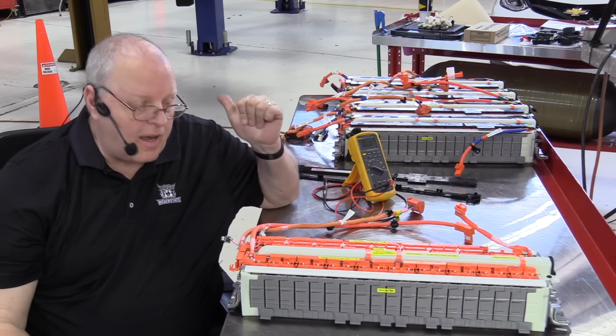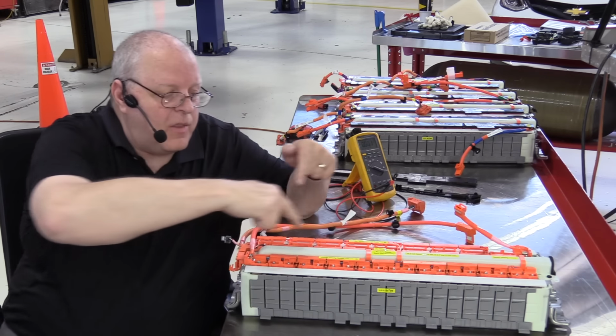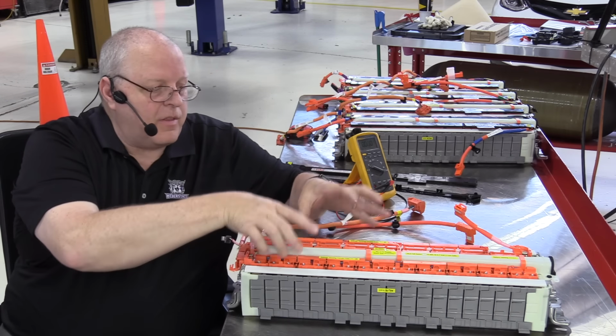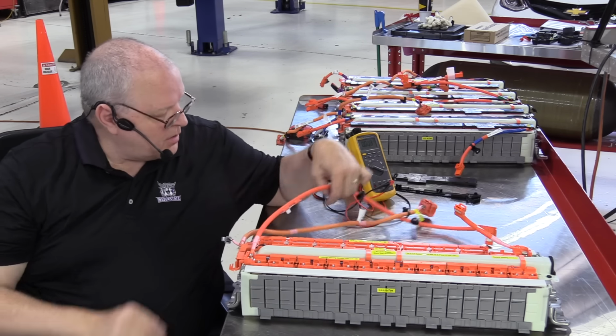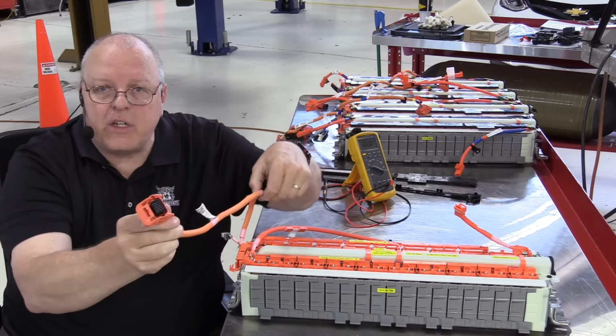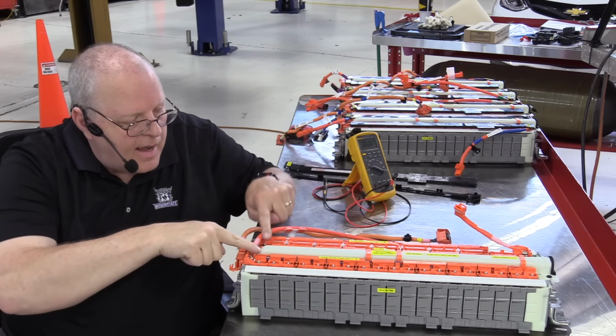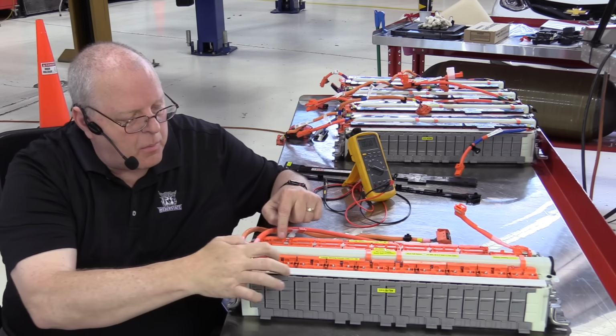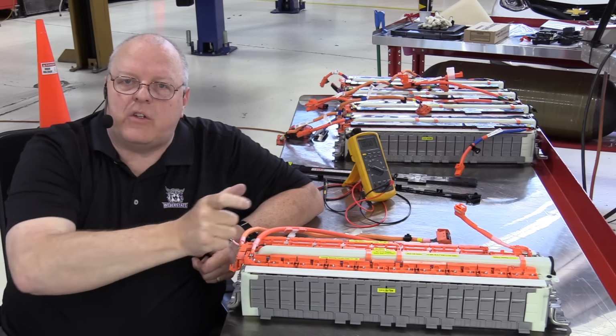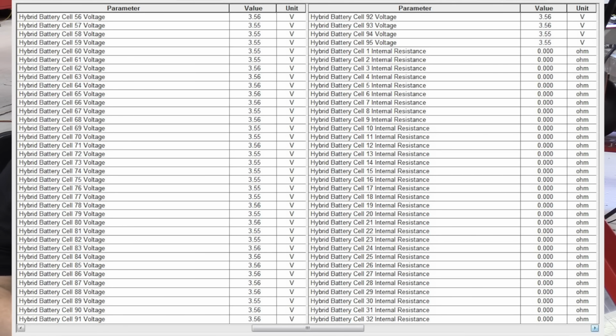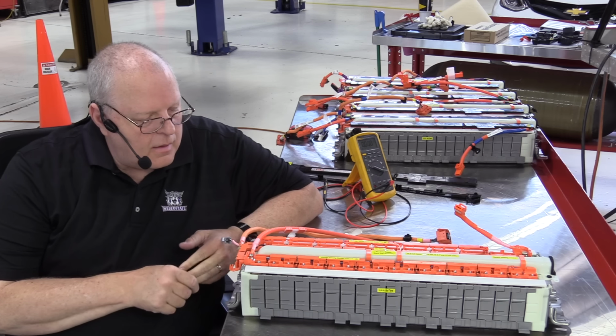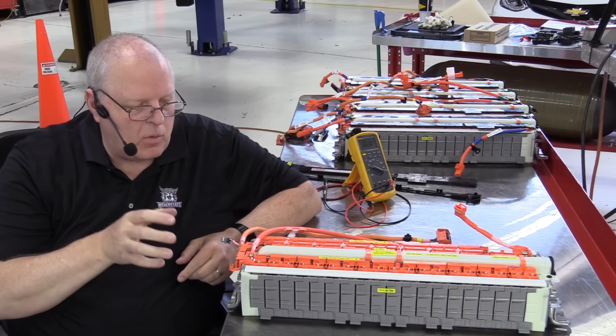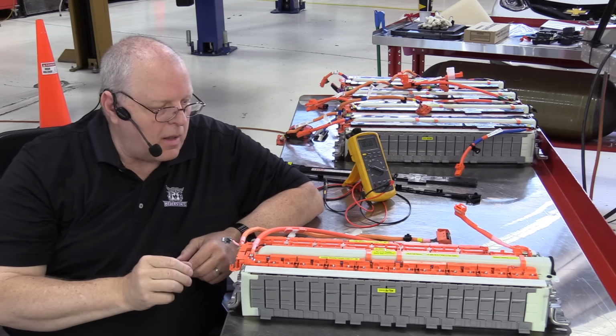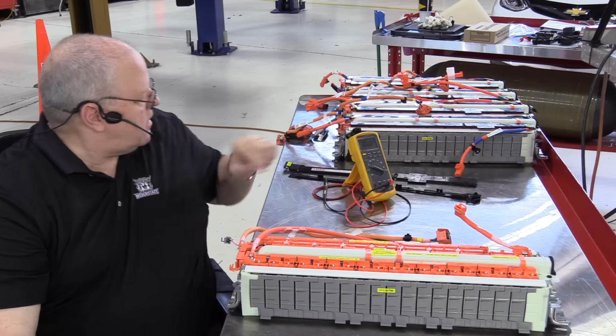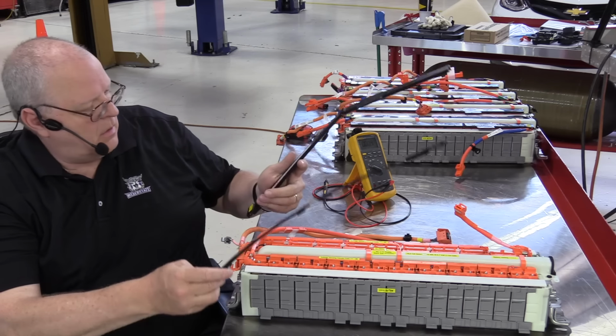So on battery stack number 1 over there, I removed all of the nuts and took off this bus bar system. The bus bar system has individual voltage monitoring circuits that run down the edges of the bus bars to measure each individual cell's voltage. If you look at this picture of a scan tool data list, you can see an example of that. Once I removed that entire bus bar assembly, which by the way has 6 temperature sensors in it, let me see.